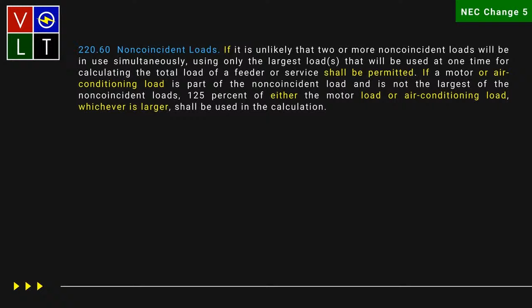That's why I said, since they put it in 220.50 and did this work here in 220.60, now, when you're doing the largest motor load and adding 25%, that air conditioning load could be the largest load. Okay, I agree. And that is your 5 changes this week.